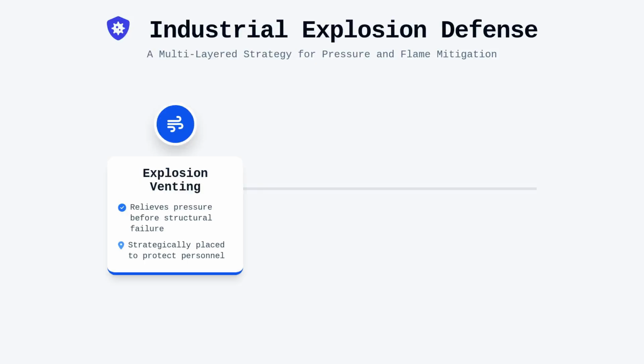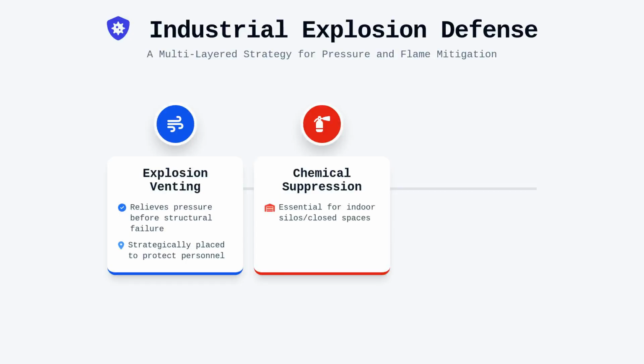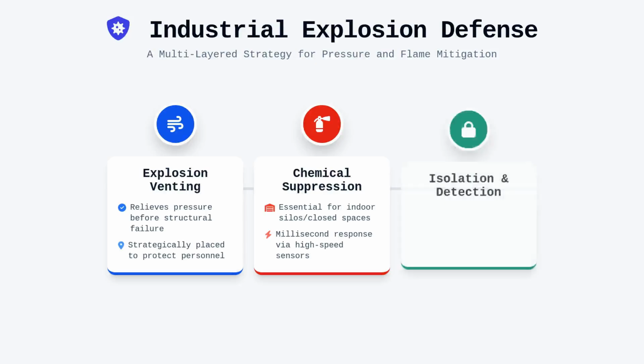In scenarios where venting is impossible, such as inside indoor silos, we turn to chemical suppression systems that detect the onset of a pressure rise via high-speed sensors and flood the volume with an extinguishing agent in milliseconds. Isolation valves are equally essential, as they create a physical barrier to block the propagation of the flame front from the machine to the rest of the facility.